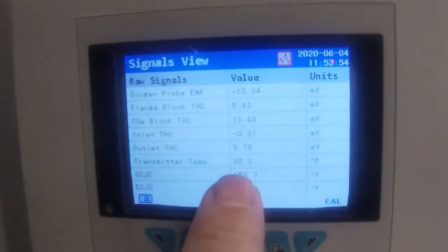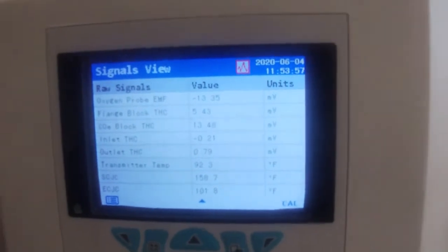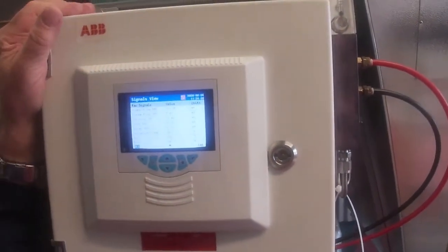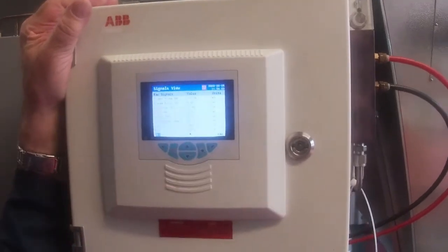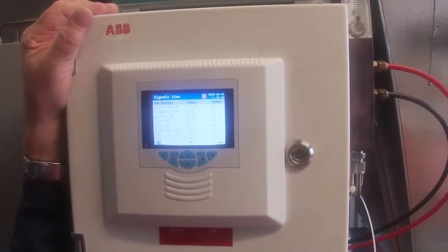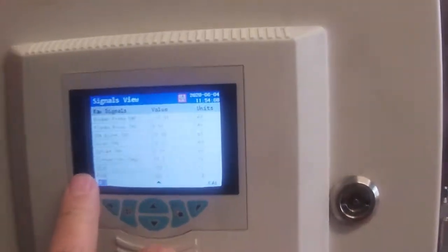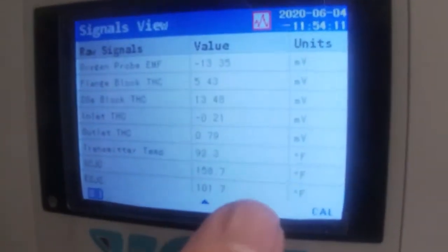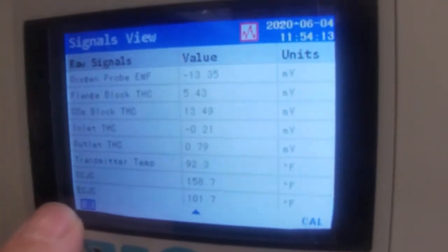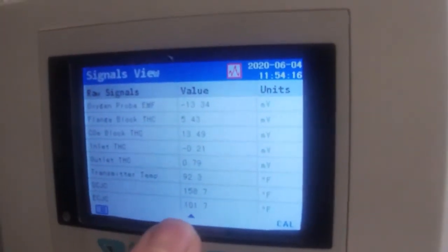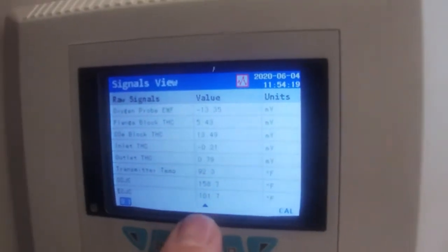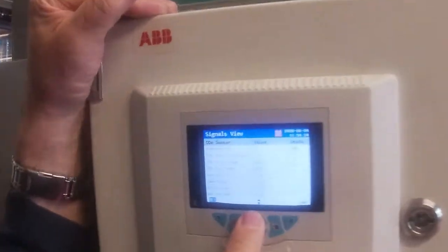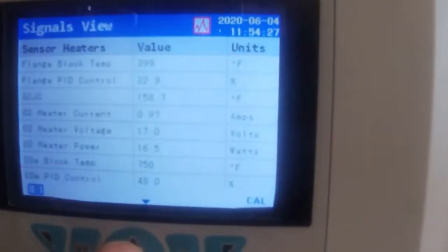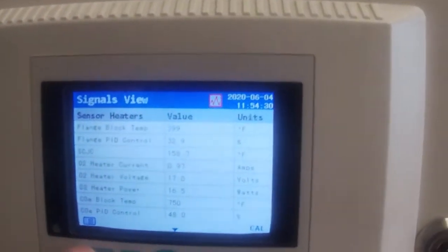The transmitter itself is sitting at 92 degrees F, and that's this thing, the electronics. So it's actually giving you an indication. So if there was something wrong there, that thing was running excessively high, it would actually be recorded and alarmed. And then the cold junction compensation is sitting at 158.7, and the electronics, this package here, cold junction compensation is sitting at 101.7. And I've run out of pages. I've only got an up arrow now, so I've got to go back up. Okay. So that's basically the sensor view itself.